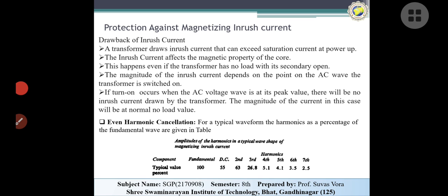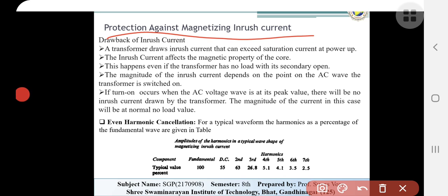Now the protecting against द मैग्नेटाइजिंग इनरश करंट, जैसे कि हमने देखा कि ट्रांसफॉर्मर में जब लोड कनेक्ट होता है तो हाई स्पाइक जनरेट होती है, तो उसको रिड्यूस करने के लिए जनरली ये प्रोटेक्शन सिस्टम होती है. तो जनरली ड्रॉबैक ऑफ द इनरश करंट इज द ट्रांसफॉर्मर draws inrush current can exceed the saturation current at a power up. Then after the inrush current affect the magnetic properties of the core. It means they have also damaged the core properties. This happen even the transformer has a no load which is in the secondary will be open. अब अगर ओपन होता है तब भी इफ़ेक्ट होती है.